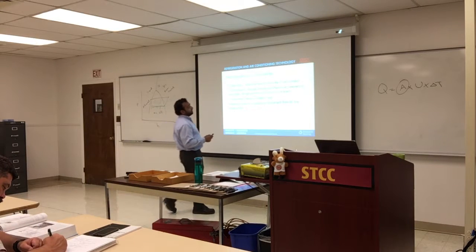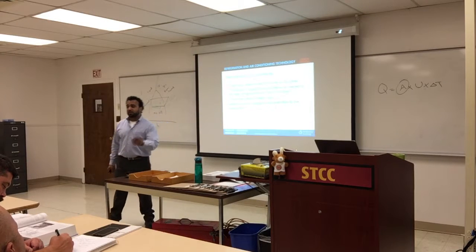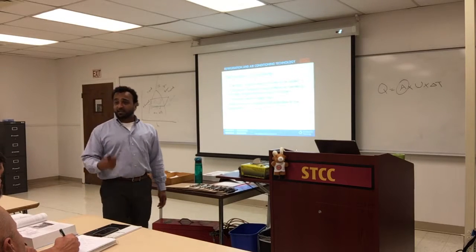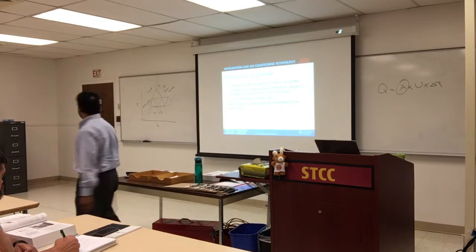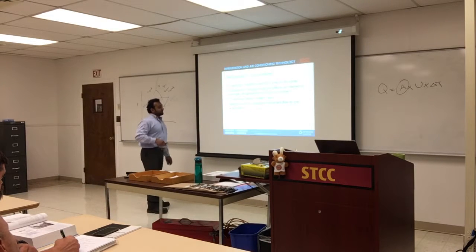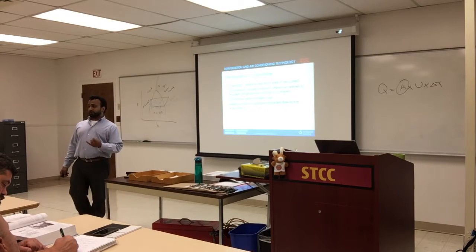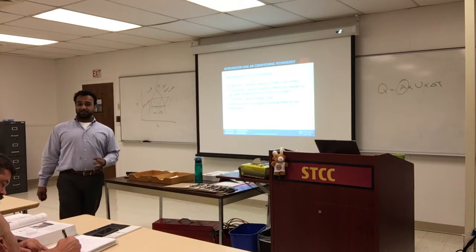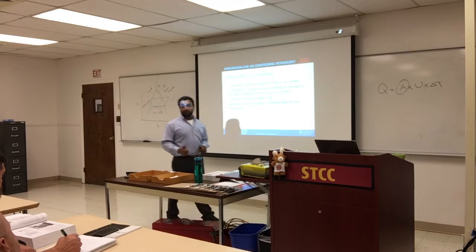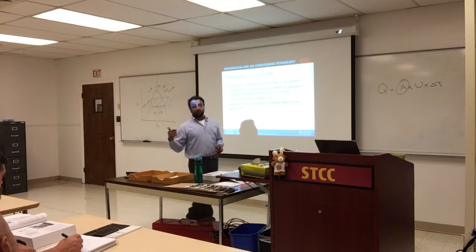The compressor creates the pressure difference that's needed to facilitate the refrigerant flow through the system. As Spencer was saying, the compressor keeps the refrigerant going. It's called the pump, and it's also adding pressure to the system. The condenser rejects the system's heat to the outside, and a metering device regulates the refrigerant flow to the evaporator. It's called the metering device, expansion valve, throttling valve, so many names. And in a heat pump, it's called a reversing valve, because it has the ability to reverse the cycle, and instead of evaporating, it will condense.